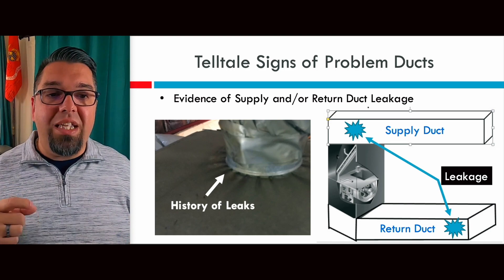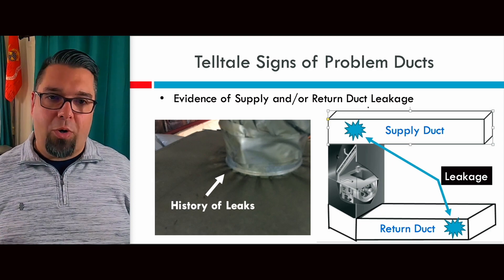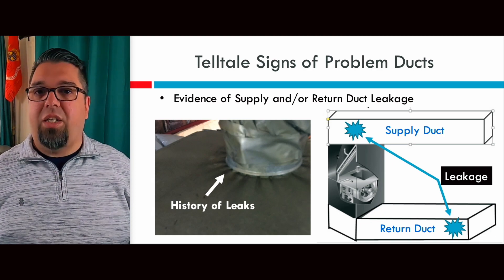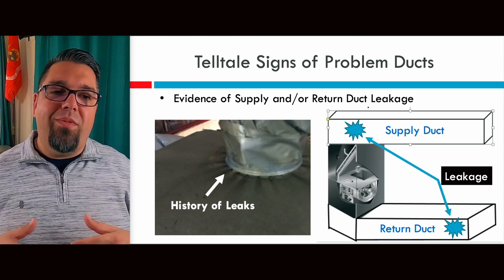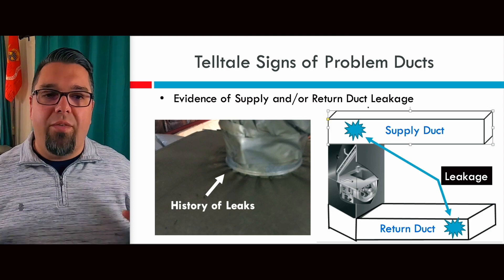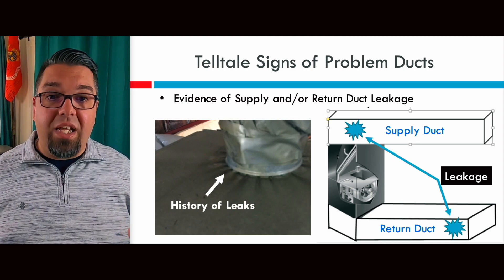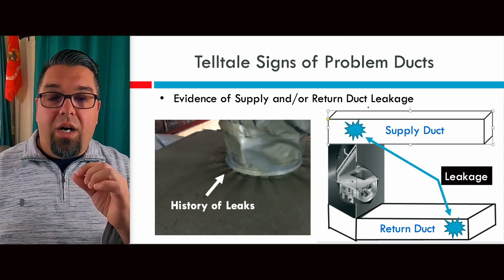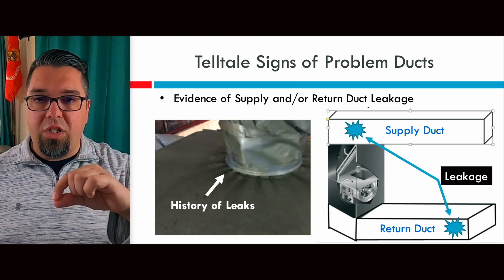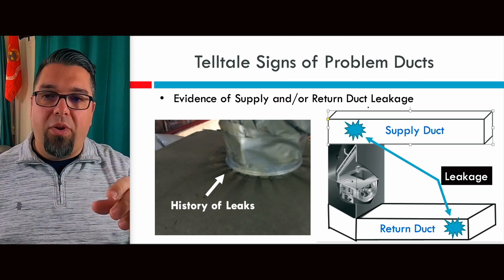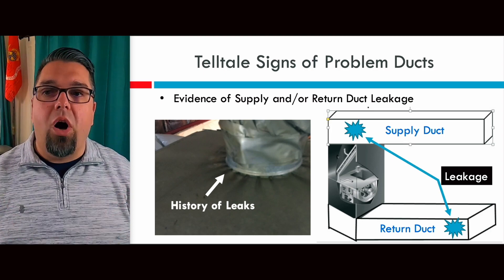When you're looking for leakage, there are some really easy telltale signs. There's the point where ducts are disconnected, broken, splitting apart, or the insulation has just disintegrated — and you can see air leakage. That's simple to see. You know when you have old R4 or older insulation that's breaking down. But take a look at the takeoffs, and if you see any sort of ghosting — a little bit of dust constantly going across — whether it's pulling air in or exhausting out, you're going to see leakage. You'll know it's there without a lot of investigation.